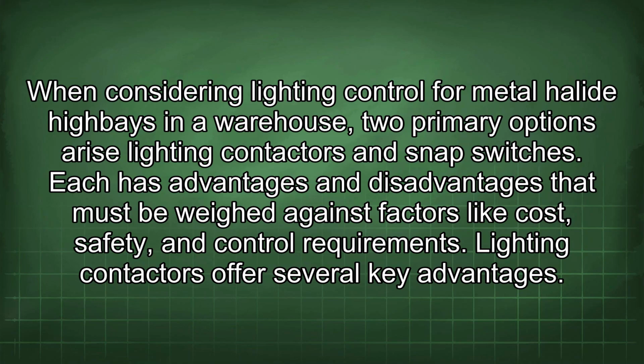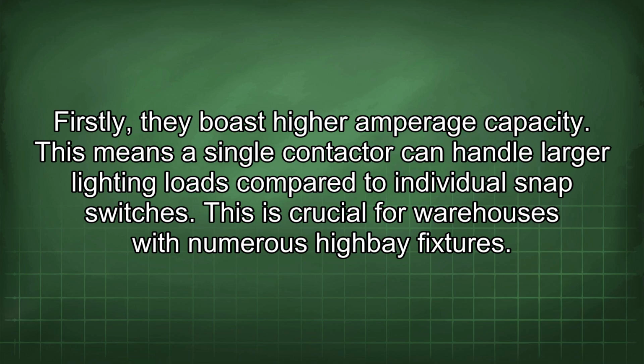When considering lighting control for metal halide highbays in a warehouse, two primary options arise: lighting contactors and snap switches. Each has advantages and disadvantages that must be weighed against factors like cost, safety, and control requirements. Lighting contactors offer several key advantages. Firstly, they boast higher amperage capacity. This means a single contactor can handle larger lighting loads compared to individual snap switches. This is crucial for warehouses with numerous high-bay fixtures.